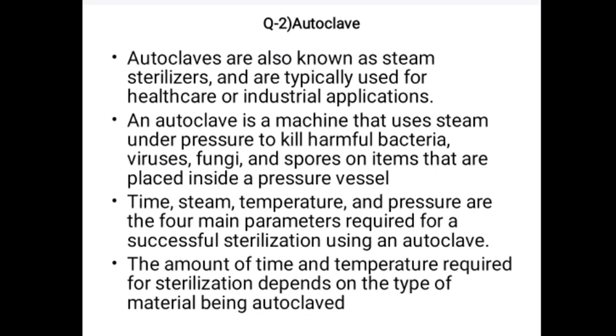Sterilization control of autoclave. This is done for determining the efficiency of moist heat sterilization. The spore of Bacillus stearothermophilus is used as a test organism. This is a thermophilic organism with an optimum growth temperature of 55 to 60 degrees Celsius, and its spore requires an exposure of 12 minutes at 121 degrees Celsius to be killed.